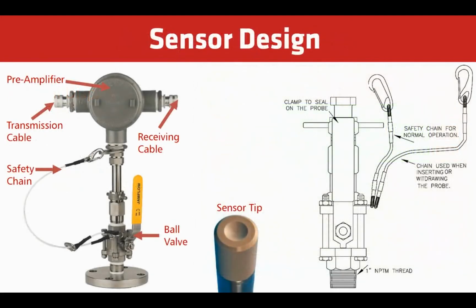Here we're taking a look at the sensor design. So as you can see, the standard over here on the left is you have a preamplifier connected to the probe shaft, goes through the gland fitting with safety chains and ball valve. So that's how it is able to be installed on a piping that is running full of fluid, or also removed without shutting the process down. There's a picture in the middle of the sensor tip with the focal optics of the tip. And on the right-hand side, it shows just a diagram drawing of our gland fitting and ball valve with safety chains assembly.